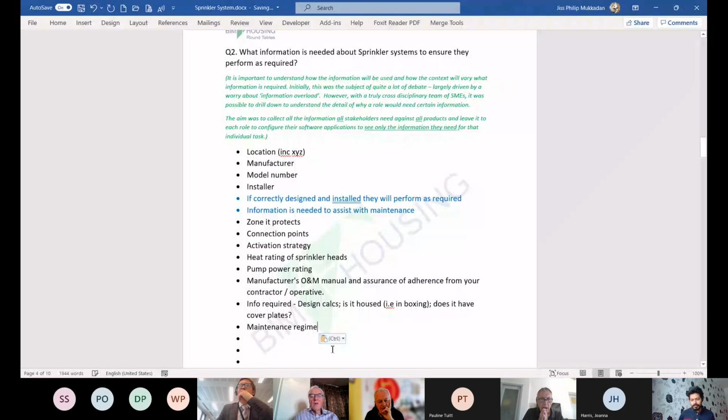What about whole life? What about how long it should last? Well, yeah. We have a lot of discussions about that. I mean, there are sprinkler systems that are over 100 years old. Typically, 50 years is not unreasonable. Some components might need replacing in that time. Pumps will probably not last 50 years. The sprinklers, no moving parts. Would there be any value in predefining that, Alan? Putting some sort of estimation on it?